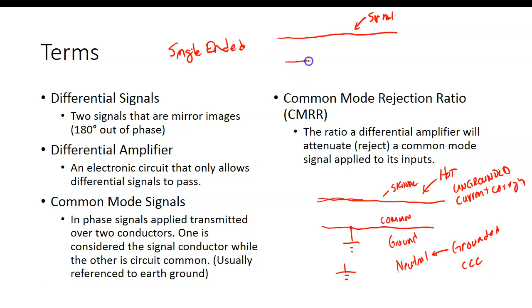So I forgot one - we have one called single-ended. It has one wire that we consider to be the signal wire, and then the other wire is considered common, or on sensors we usually reference this as earth ground. This is the way we've sent signals for years and years. So the top one is single-ended, and the bottom one is power, since we started talking about hot and neutral.